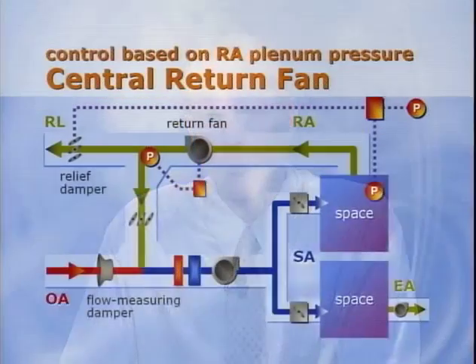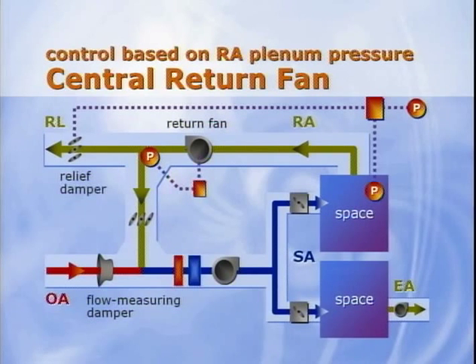At the same time, it must be remembered that under a separate control loop, the supply fan is forcing air into the duct to maintain desired supply duct pressure. Let's look at a return fan system first. The return fan, which operates whenever the supply fan does, pulls return air from the occupied spaces and pressurizes the diverting plenum in the rooftop unit. Air from this plenum either passes through the return air damper into the mixing plenum or exits the building through the relief damper. With a return fan configuration, the fan is physically in the return ductwork.